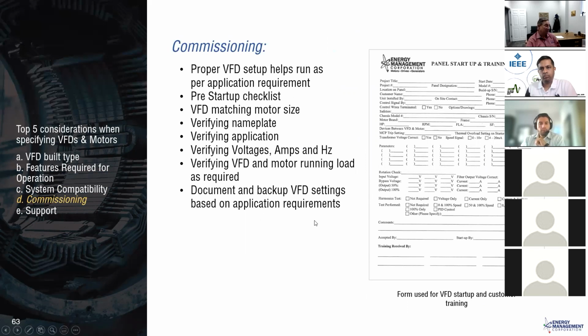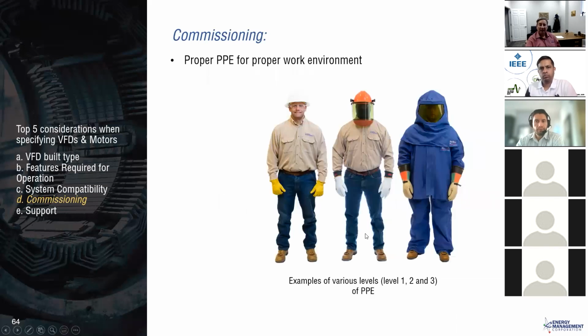We just did a medium voltage project with, I think, three 1,000 horsepower medium voltage drives. Because they've had problems with other drive systems in the past, they asked us, as part of the commissioning process, to do vibration analysis and to do the bearing current and dV/dt checks as part of that process.